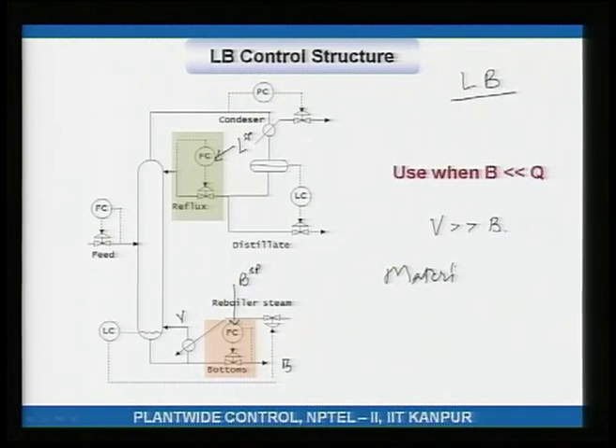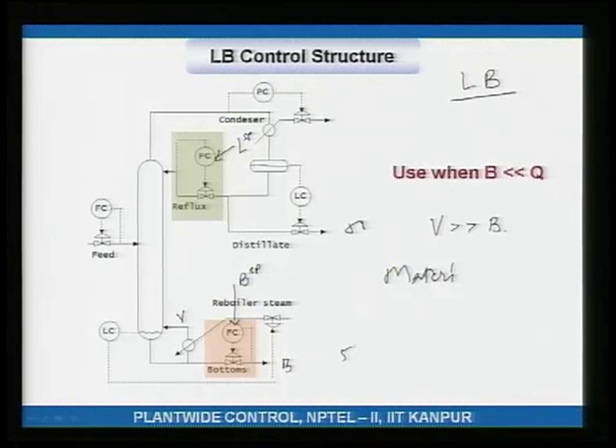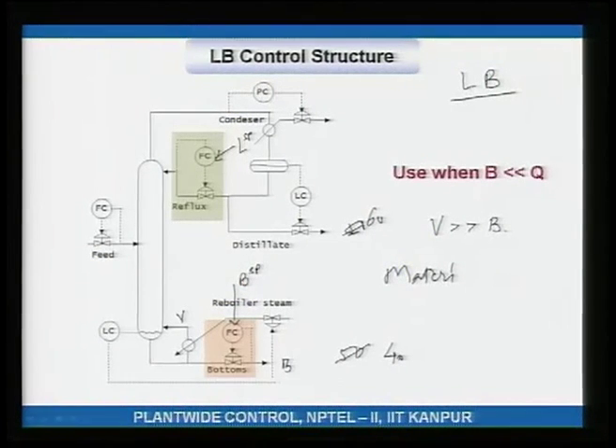The LB structure is again a material balance structure. When the operator increases or decreases the bottoms set point, they are directly adjusting the material balance across the column. For example, if the total feed is 100 and you change the bottoms from 50 to 40, then 60 must go up the top.